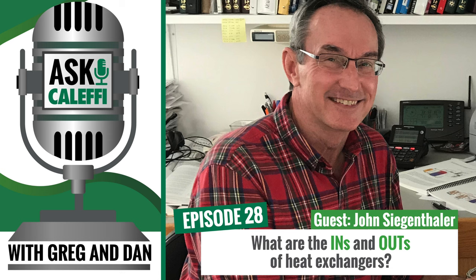Right, right. Yeah, sizing's a pretty important thing when it comes to anything. You know, I feel in any project. It is. And the good news about sizing today, most of the companies that sell heat exchangers have sizing software that's available to designers or engineers. Most of it's free. You can go online and either download the software or use it directly online. And you can basically put in what I call the what if conditions. What if my source water is at 120 degrees and I want my load water to be at 110, and put in the flow rate, and it will size heat exchangers based on those inputs.